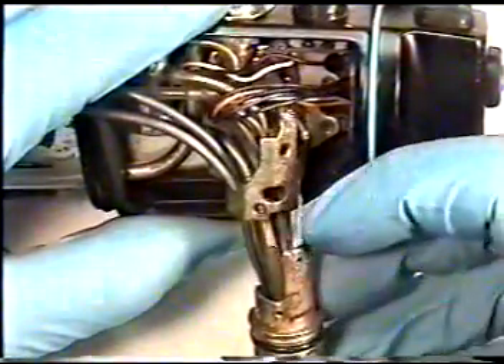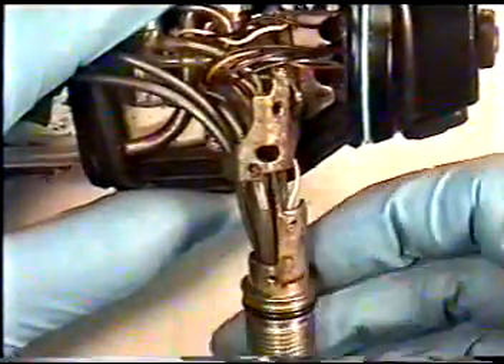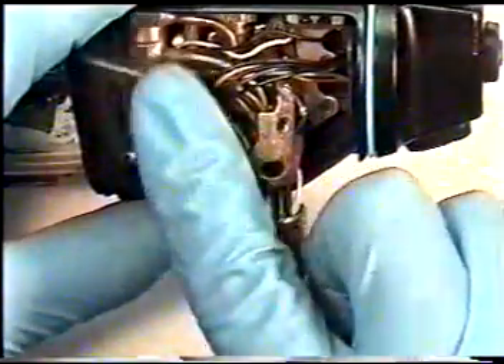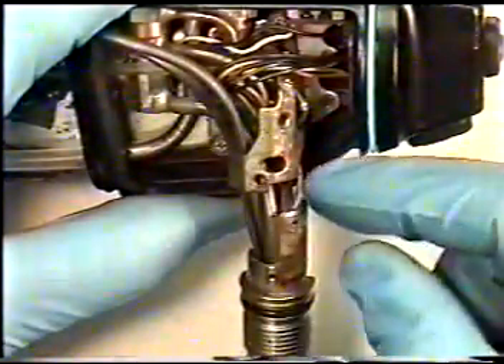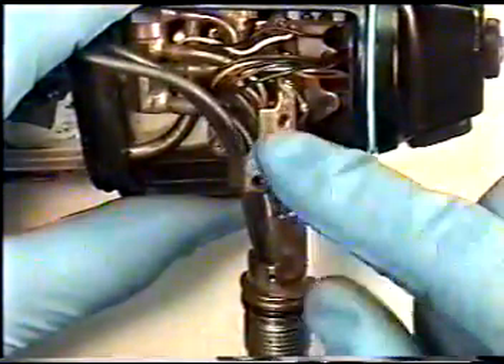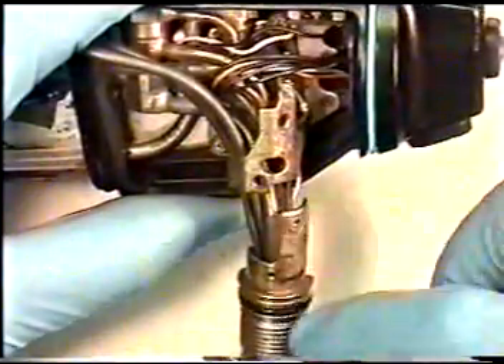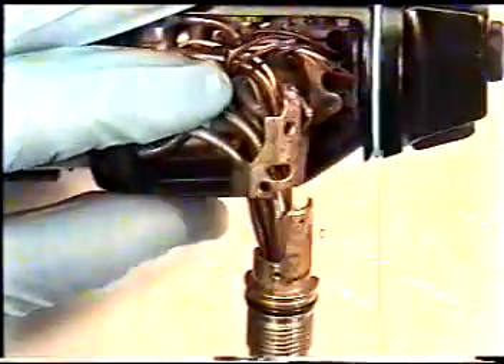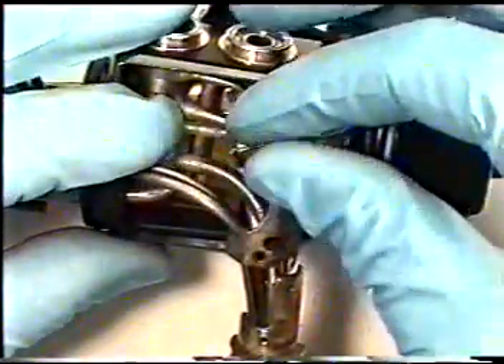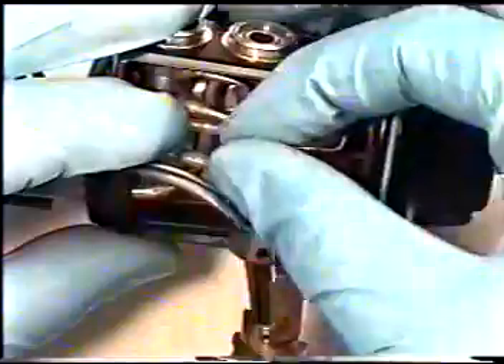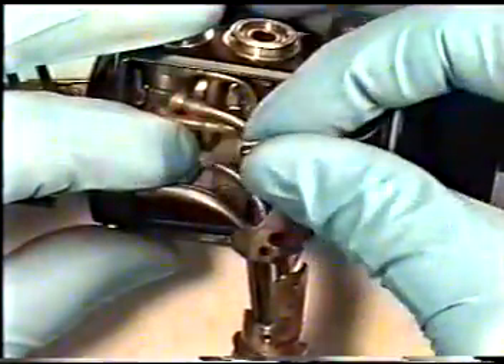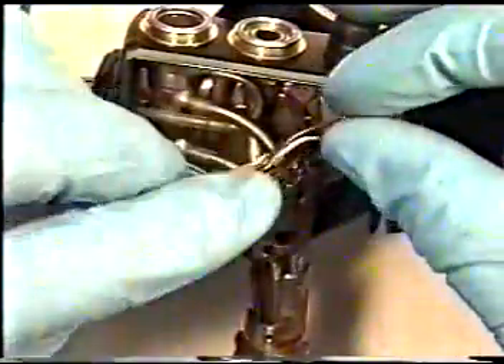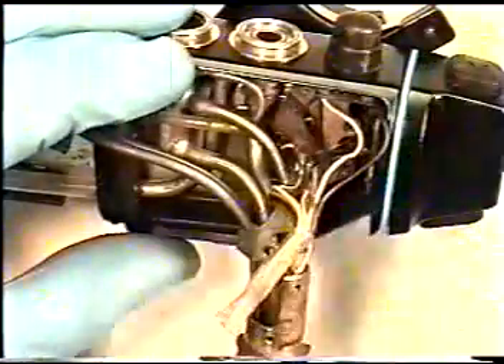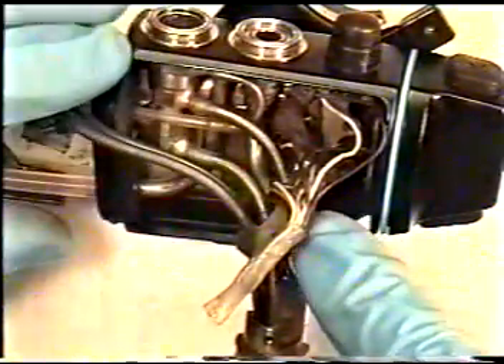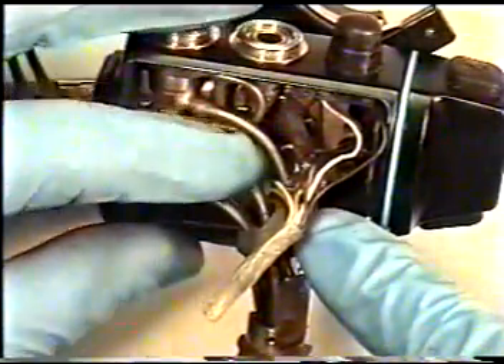We will need to remove the suction tubing from your umbilical control section in order to be able to remove our illumination light guide bundles and replace with the new illumination light guide bundles. It is too tight inside this umbilical cord, so we must remove our suction channel. Pull out your wire harness if it is a video scope or a fiber scope. Be careful not to damage your image bundle if it is a fiber scope. Pull wires up and away. We will need to remove our retaining body bracket in order to gain access to our suction control pipe.